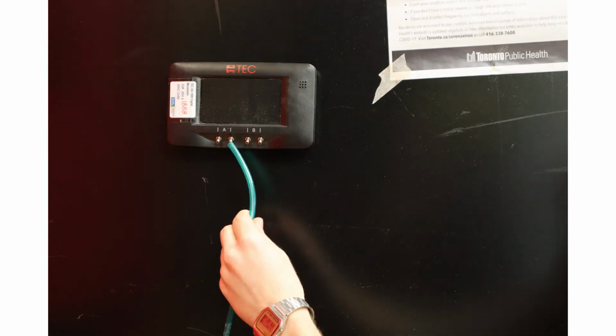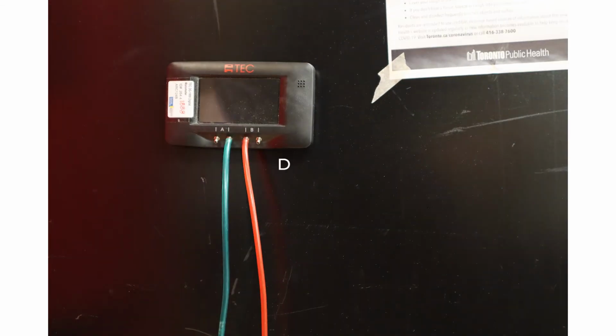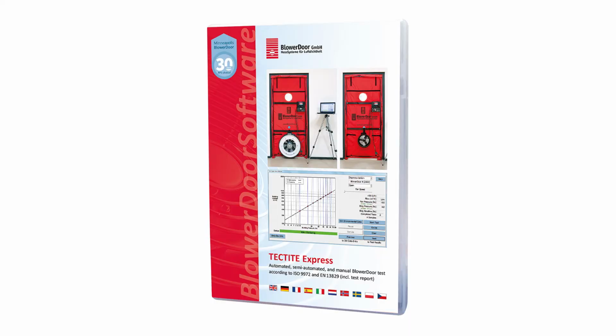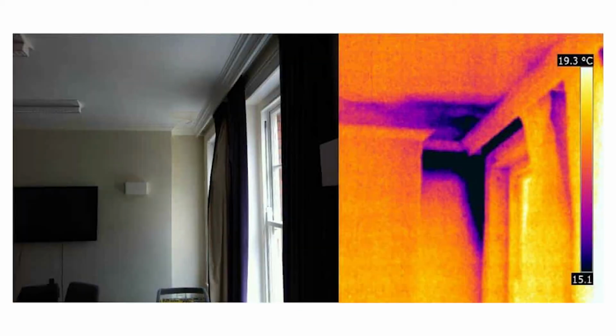Next, attach the manometer to the frame using the mount, and the green tube from the outside to A, and place the red tube to B. The manometer at Ryerson is the DG1000. This manometer has a setup guide as well as various measuring options. Software such as TECTITE Express can be downloaded and the results can be plotted instantly. Take photographs of areas of the building that could be areas of air leakage.